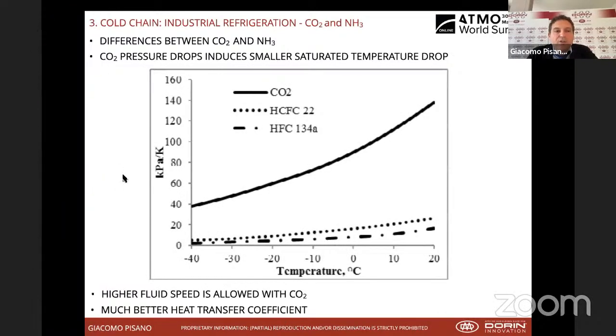Another interesting feature is pressure drops. Normally, CO2 is inducing smaller pressure drops. This means that a higher fluid speed is allowed with CO2, and this brings a very nice heat transfer coefficient. This is clearly a comparison between R22 and R134a, but maybe we can assume that R22 has a similar heat transfer coefficient to ammonia. And you can see that CO2 is bringing a very nice K factor, a very good heat transfer coefficient.